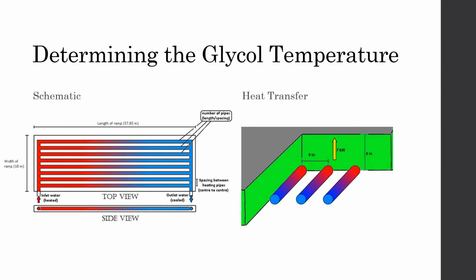It was decided to divide the piping into 39 loops, each 3 ramp lengths long, parallel to the library wall, and can be seen in the figure on the left. Industry standards suggest that the piping within the ramp be spaced at 6 inches apart, center to center, and at a depth of 6 inches beneath the ramp surface.